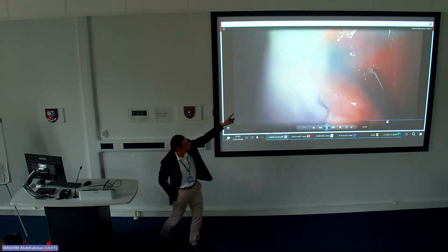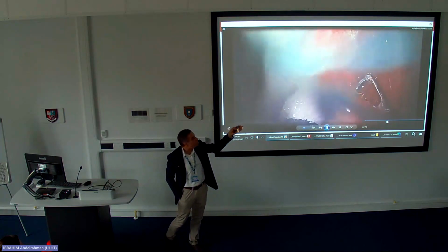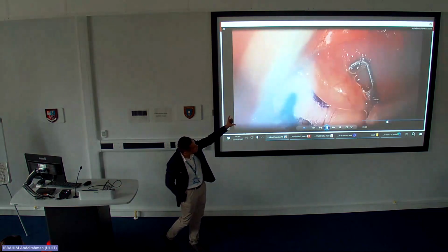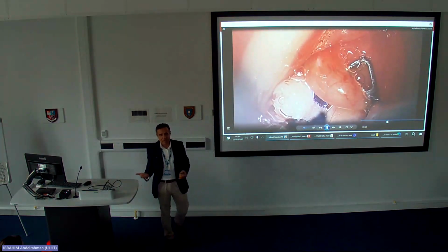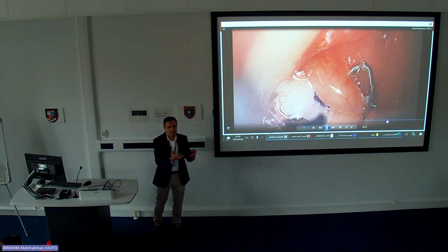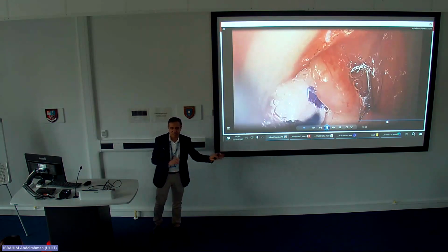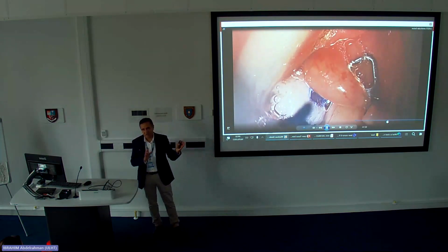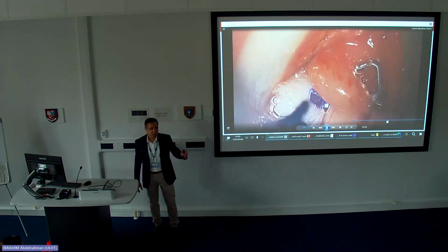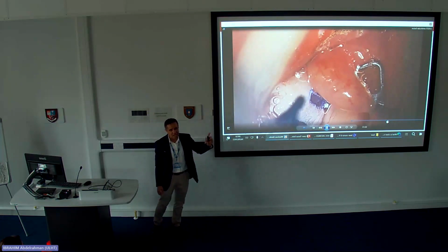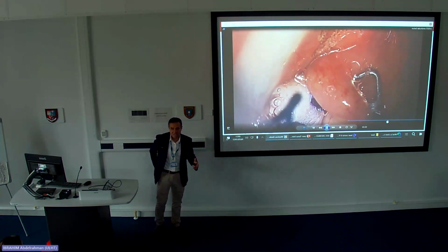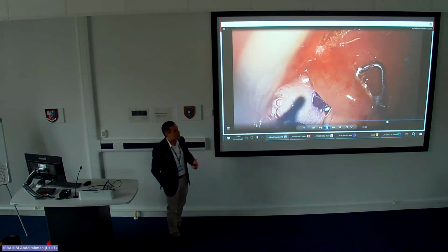You can see when I did this, I found it was not ablating, it was more like coagulation. So I asked them to increase the size, and I made it more semi-linear and increased the watts. So playing with these parameters will give you the effect that you want. I prefer low watts to see the coagulation effect. If you find the coagulation effect is there, that's okay. Increase the watts up. If you find it's just cutting from the start and it's good, that's good for you. A lot of the time the machine itself is a little bit higher, so it sets higher than you expected, or sometimes lower. Don't depend much on what's in the setting.